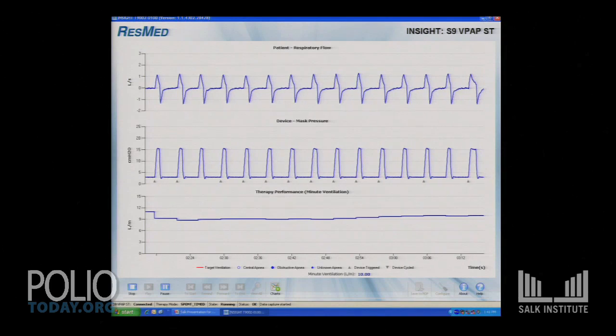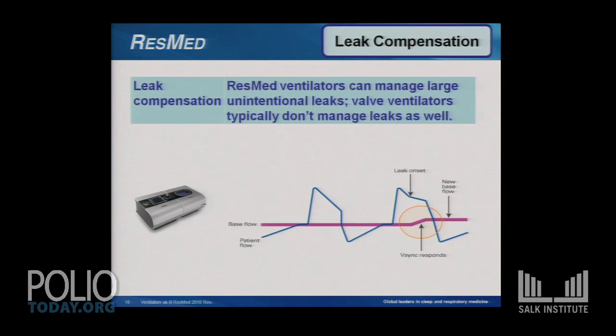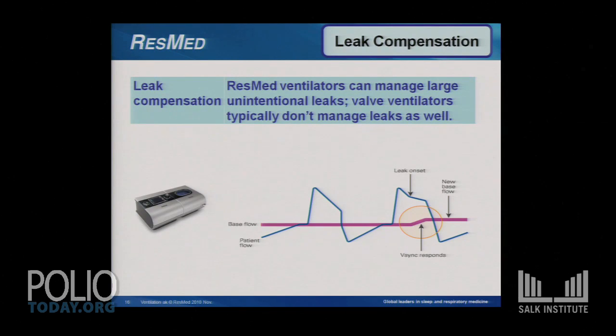Okay, now we'll see if we can close out of here and go back to a few more slides. And Sam has graciously agreed to stay up here with me. Oh, shoot. Oh, sorry. Because I do have another thing I wanted to show you. Oops, there we go. Okay, so let's take a look at that. That leak compensation, the device is watching that baseline flow. And as soon as we change the baseline flow, because we created that big leak, we opened both ports on his mask, it took just 2 breaths for it to recalibrate and adjust that baseline flow. So his next breath was back in synchrony.